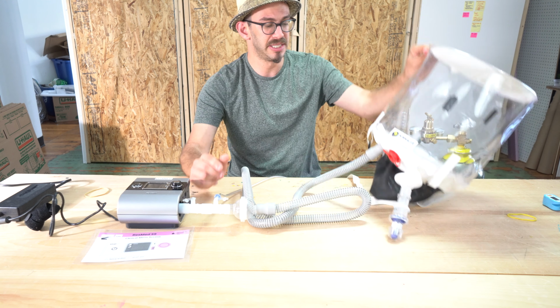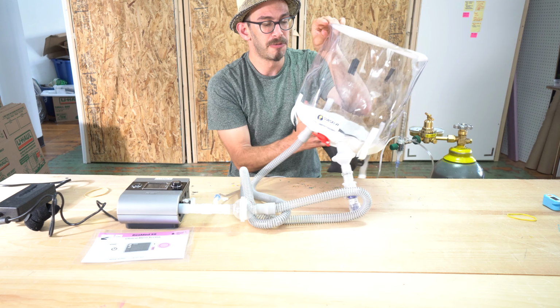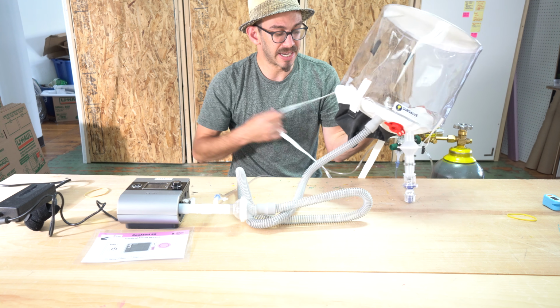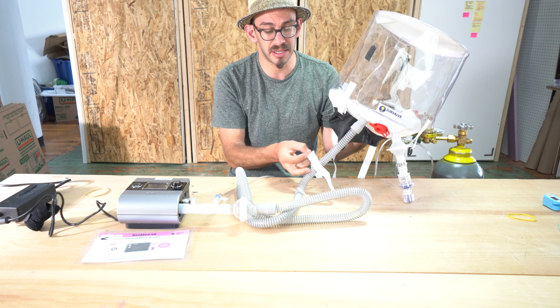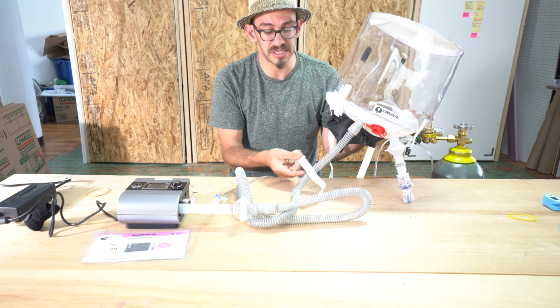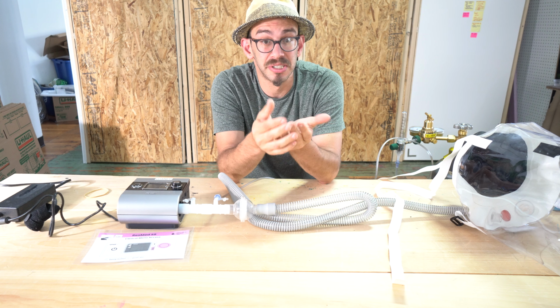Another thing I should mention is when you put this helmet onto your patient, do it without turning on the CPAP. And the reason for that is you want to first tighten these straps under the patient's arms. If you turn on the CPAP without tightening these, the helmet will puff up and apply pressure to your patient's nose and mouth, and this neck seal will push and get in the way. It's not a critical problem, but it is uncomfortable for the patient and it is avoidable.